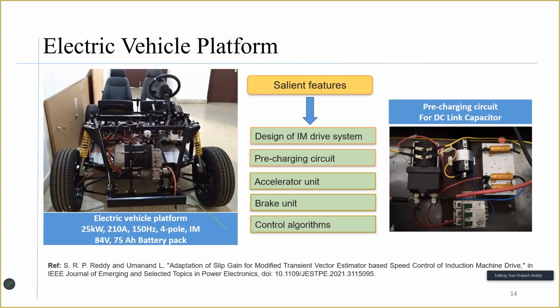So I have designed the pre-charging circuit for the DC link capacitor, because when the battery is directly connected, interfaced to the motor using a DC link, there is a huge chance of surge currents flowing through that, because the capacitor is initially uncharged.